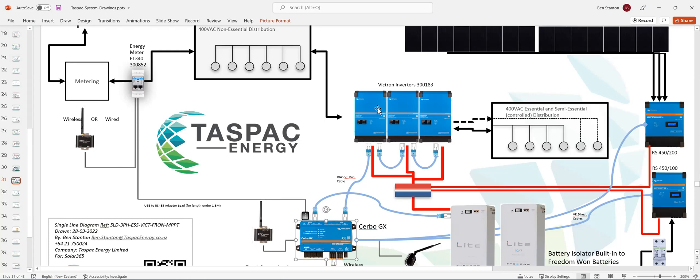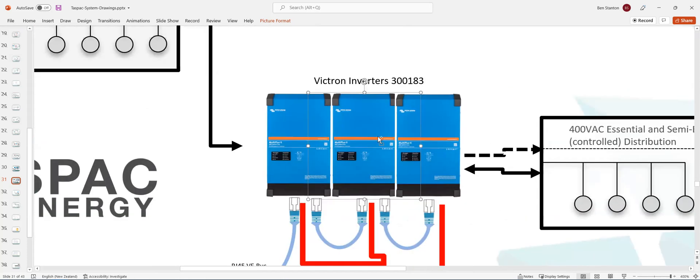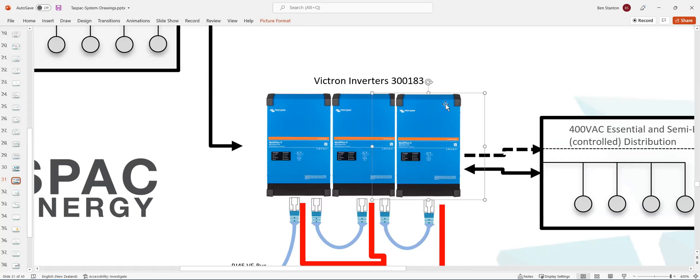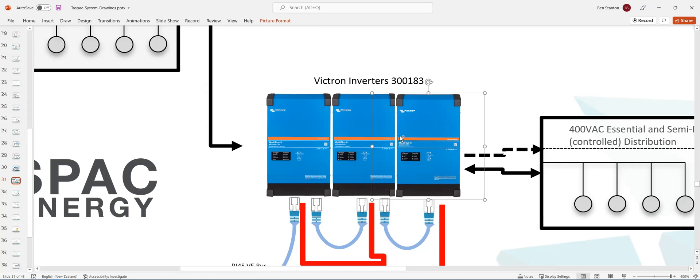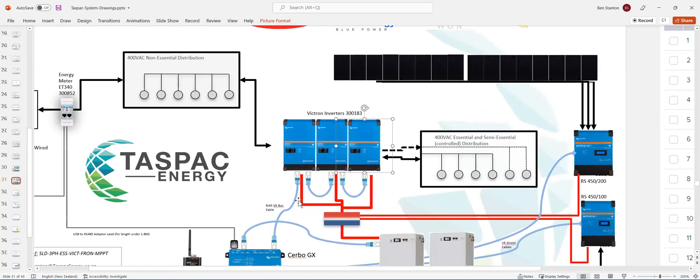So let's come back to the Victron inverters. The Victron inverters, one inverter per phase. So you're wiring them up as single phase inverters and one inverter per phase. The neutral on the inverters is common. And the battery connections are also common. So your positive and negative from your battery are also common.